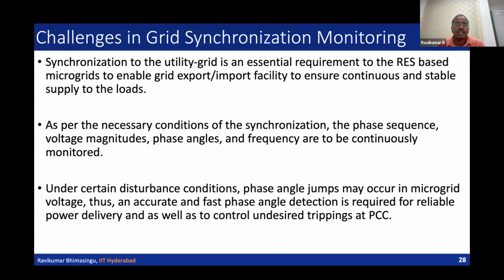So what will happen under certain disturbance conditions? The calculation of these quantities will be inaccurate, and if you have inaccurate values, proper synchronization is not possible. That's why accurate and fast phase angle detection methods are required for reliable power delivery as well as to control undesired trippings at the PCC. PCC means point of common coupling.